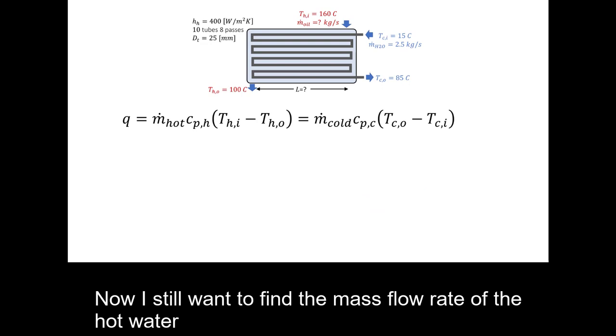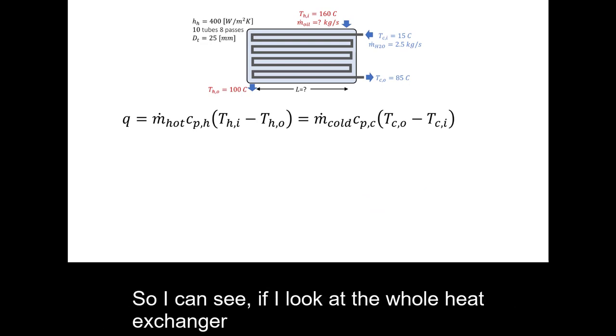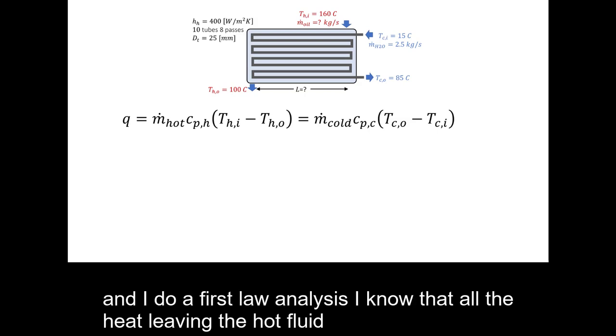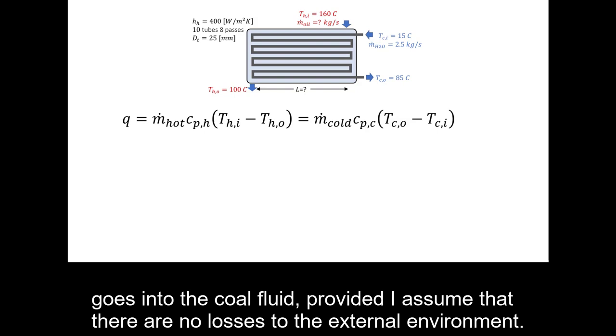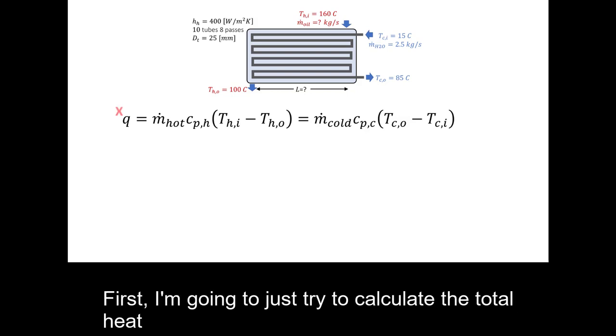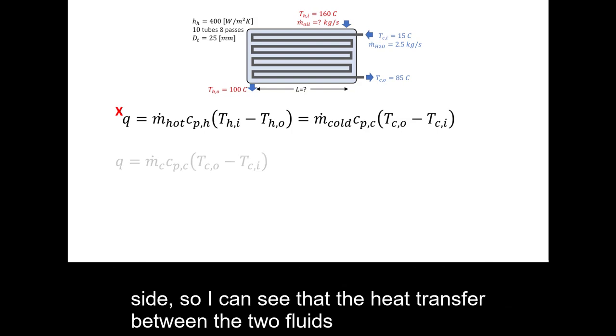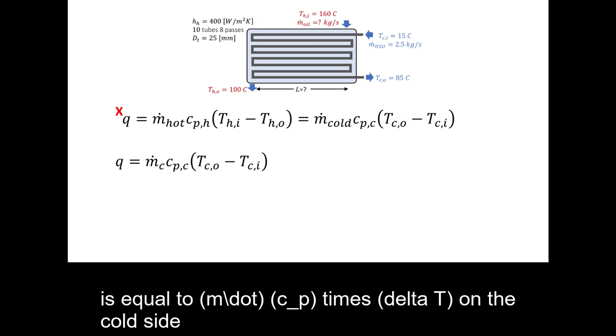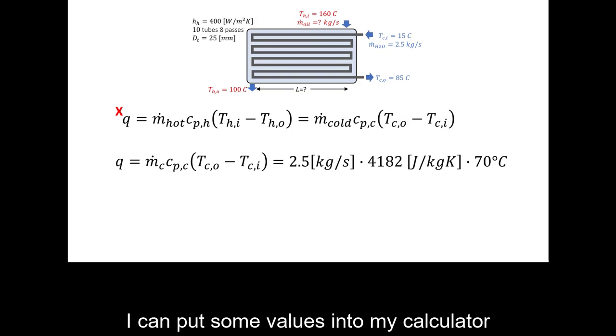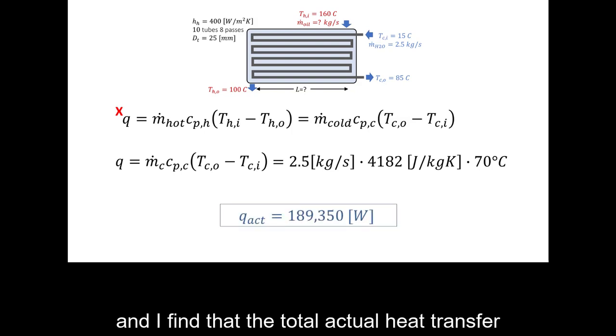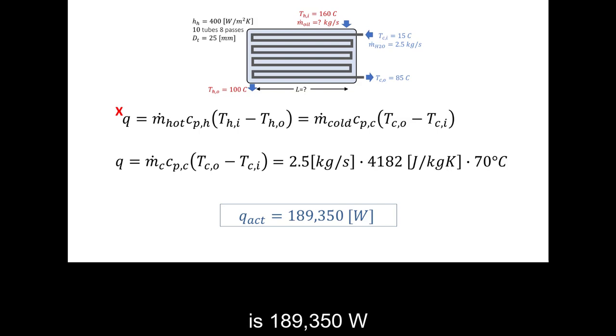Now I need to find the mass flow rate of the hot oil. Looking at the whole heat exchanger and applying a first law analysis, I know all the heat leaving the hot fluid goes into the cold fluid, assuming no losses to the surroundings. Since I know everything on the cold side, the heat transferred is Q = m_dot · Cp · ΔT on the cold side. Plugging in values, I find the total actual heat transfer is 189,350 watts.